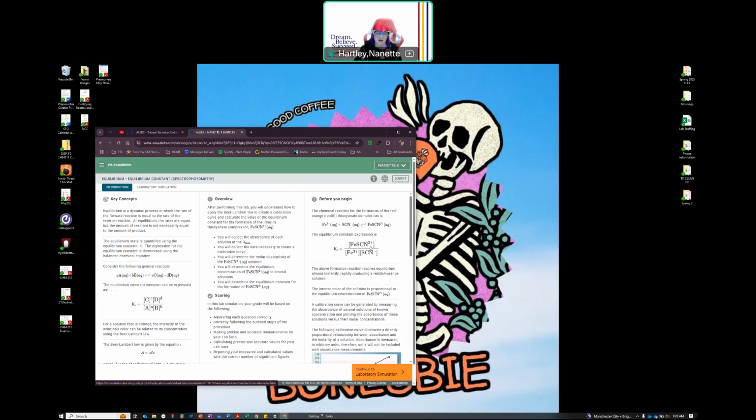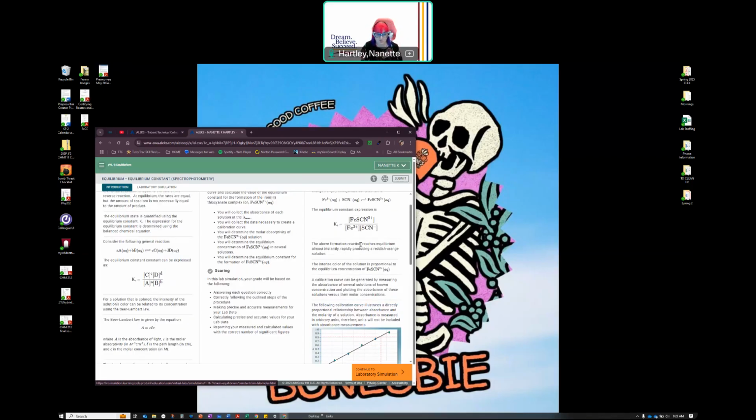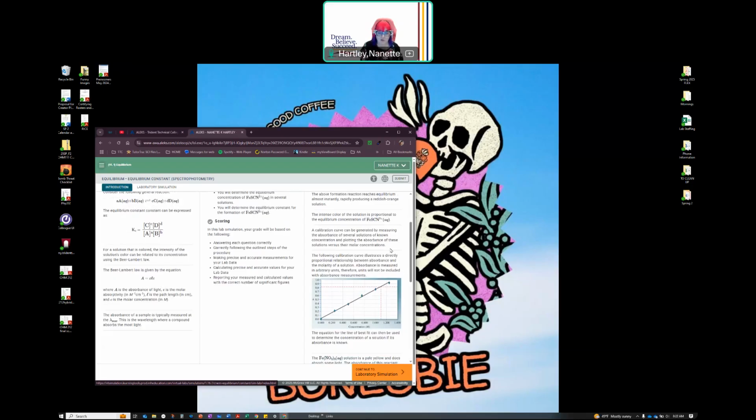So we'll be able to find what our K is for each run. And so we can do this for multiple points, determine what the K is for each of those points, and then see what the average is of each of those points, once we've determined what those values are based on our calibration.